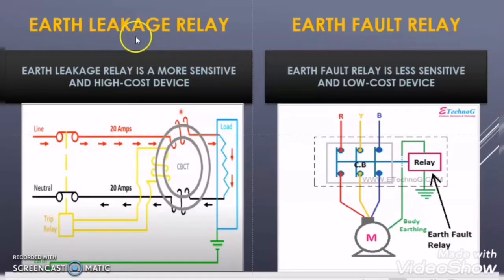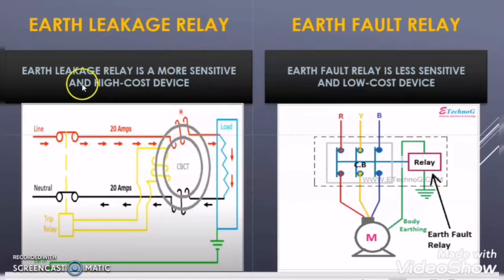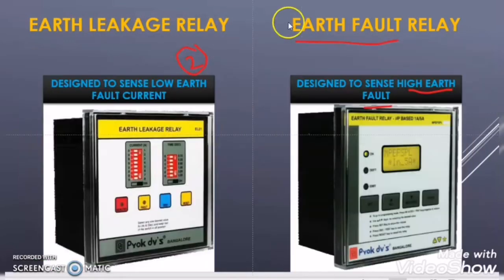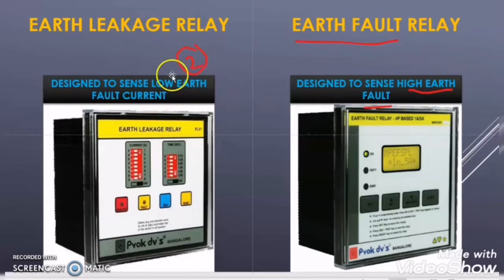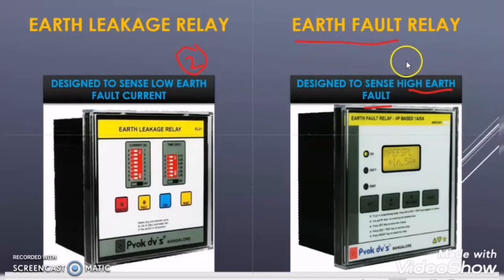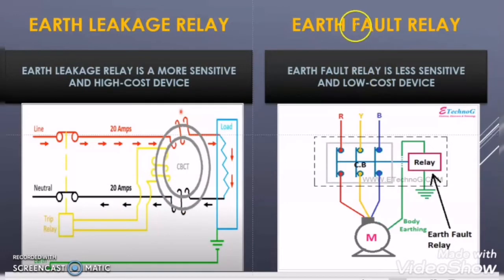The next difference is that the earth leakage relay is more sensitive and has higher cost, while the earth fault relay is less sensitive and has less cost. The earth leakage relay has to sense low earth fault current, so it must be much more sensitive. The earth fault relay has to sense high earth fault current, so it can be less sensitive. Because the sensitivity is high for the earth leakage relay, its cost is also more.